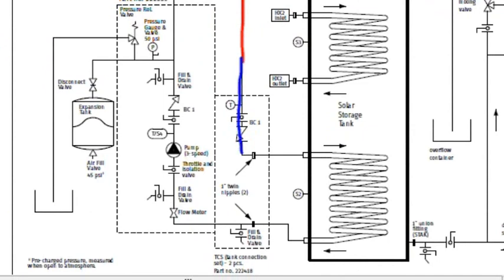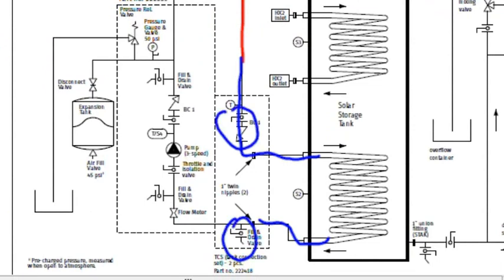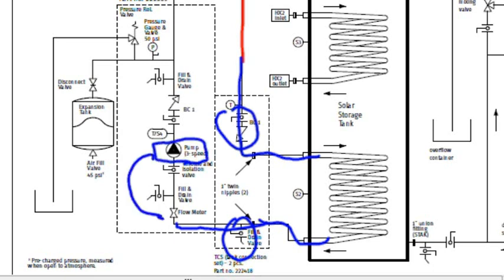So there's a check valve, flows into here, comes out. A drain valve and then another possible drain valve right here, just to shut off that I can open and close to let fluid flow. Flow meter, which tells me the velocity. I want to match the three speed pump right here to be the same speed that's most efficient for collecting that solar energy.